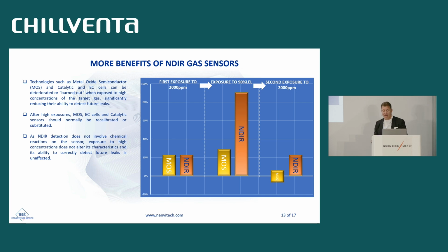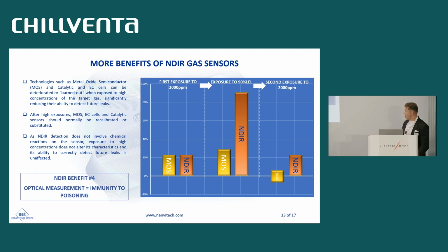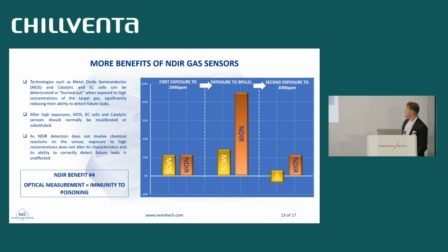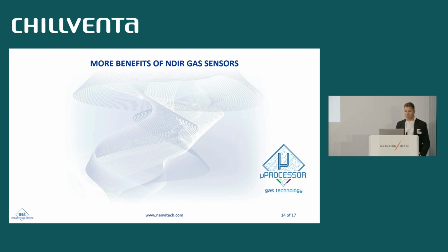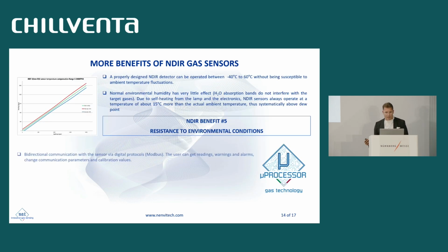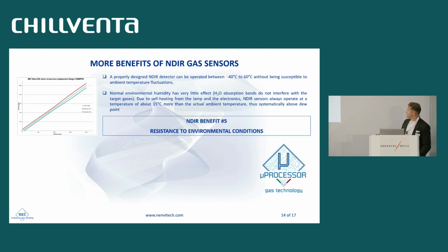In fact, typically, after a high exposure, an MOS sensor requires recalibration, while the NDIR sensor can be exposed no matter how much quantity of the target gas, and it will always maintain its calibration. That is called immunity to poisoning, and therefore the sensor can be exposed to several leaks without having to be recalibrated. I'll go shortly on that.